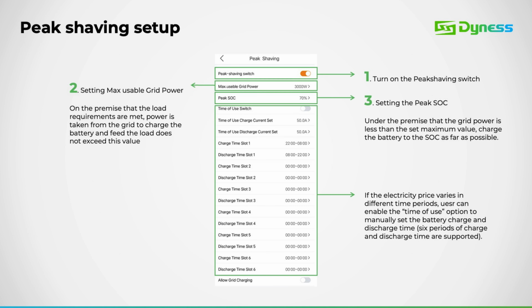Here's an illustration of the peak shaving mode. On this page, you can establish the maximum usable grid power along with the peak SOC percentage. This operates on the same logic as battery reserve. Additionally, within this mode, you can designate charge and discharge time slots for utilization as needed.